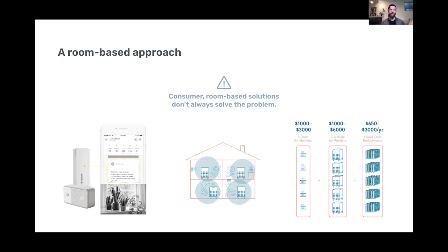So what is the work your air conditioner did? It did both the work of removing moisture, and that took effort, that took energy, but it also changed the temperature. And you can actually change the work that an air conditioner does depending on the amount of CFM moving through the system. You can adjust the sensible to latent ratio to say, I'm in a dry climate. I care more that this air conditioner is sized only for the sensible portion of the load to get my set point, because I'm in Las Vegas and I want a cold home, but I don't want to remove moisture. So I'm going to bias towards a totally sensible ratio of this air conditioner versus latent. I live in Florida.